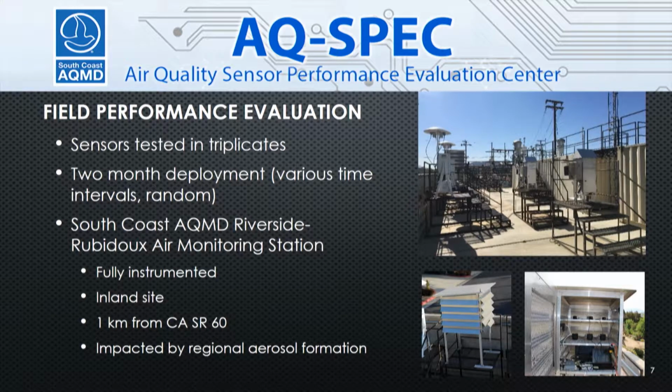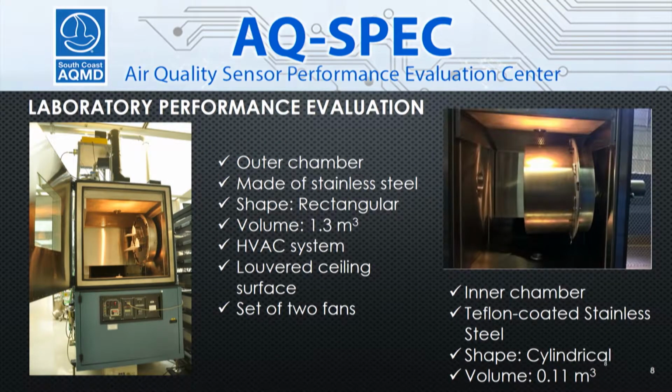And during that time, we collect the data, we time match it to the reference instrumentation, and then we run regression statistics, provide that evaluation report on our website. All those results are publicly available on our website. The chamber: if the devices perform well in the field, they will then be taken to our laboratory.